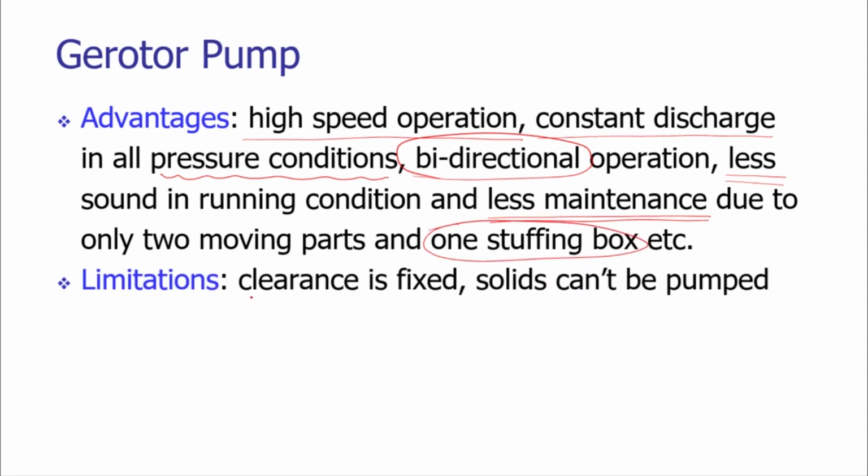However, G-rotor pump has certain limitations. The clearance is fixed, so we cannot modulate, we cannot vary the eccentricity, we cannot vary the offset between the rotation. The clearance is fixed. These pumps are not suitable to pump the solid or the semi-solid fluids. If the solid is like cherries or the tomatoes or the slurry of cherry or tomato in the food processing industry, it's very difficult to convey them.